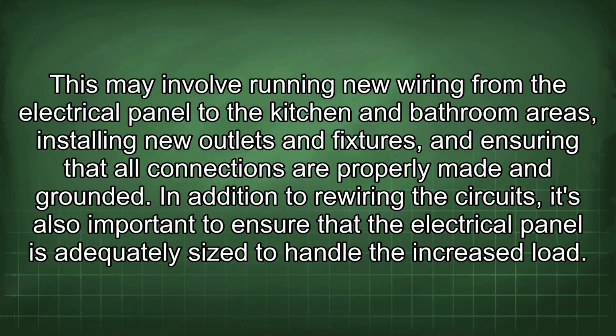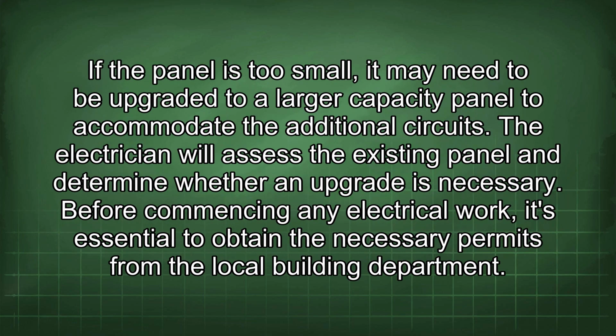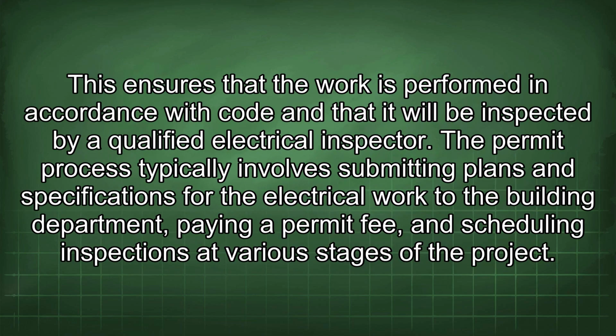In addition to rewiring the circuits, it's also important to ensure that the electrical panel is adequately sized to handle the increased load. If the panel is too small, it may need to be upgraded to a larger capacity panel to accommodate the additional circuits. The electrician will assess the existing panel and determine whether an upgrade is necessary. Before commencing any electrical work, it's essential to obtain the necessary permits from the local building department. This ensures that the work is performed in accordance with code and that it will be inspected by a qualified electrical inspector.